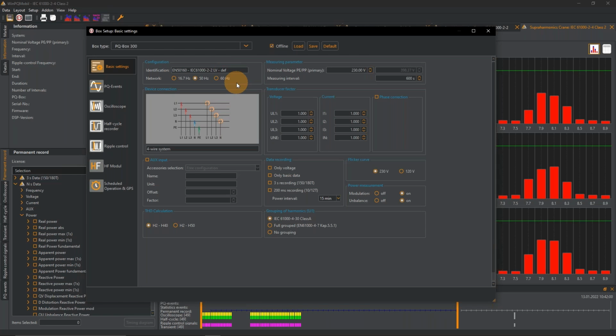I would always go with this one because this also includes our up to 150 kilohertz. So when measuring, at first step, I would always consider the whole bandwidth. With this method, you don't exclude certain frequency ranges in advance, which might be useful for later investigation. So measuring, please, I would recommend go with the 2-2, which provides limit values up to 150 kilohertz, because you can change your report setting afterwards, and you can always deactivate parts or omit measurement data of your original recording.